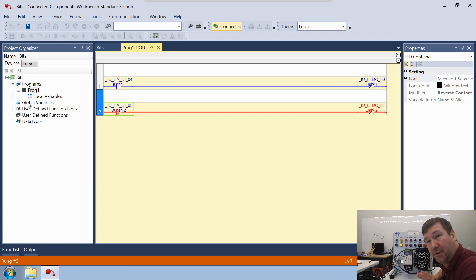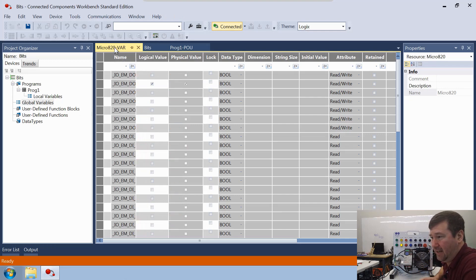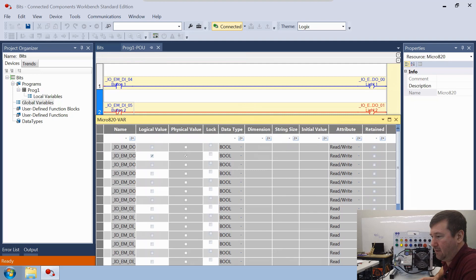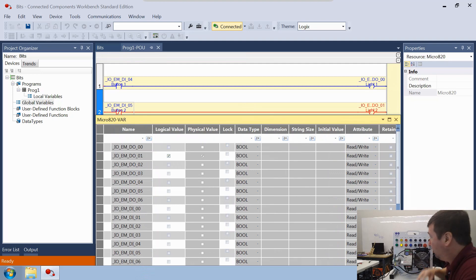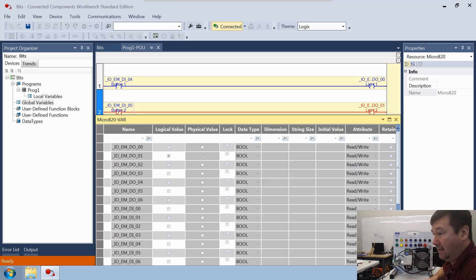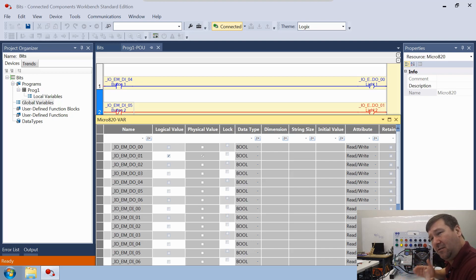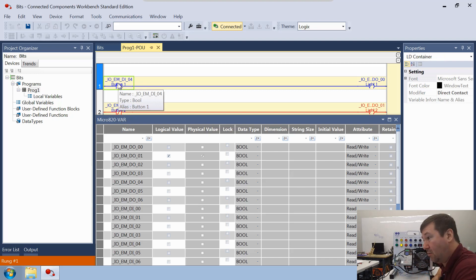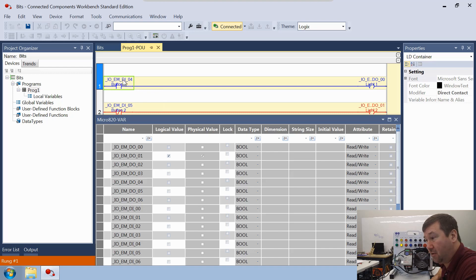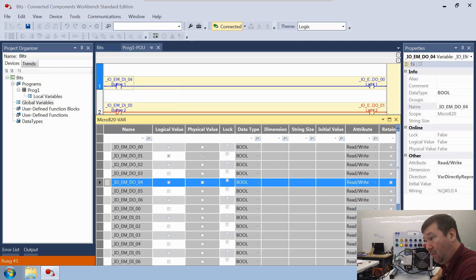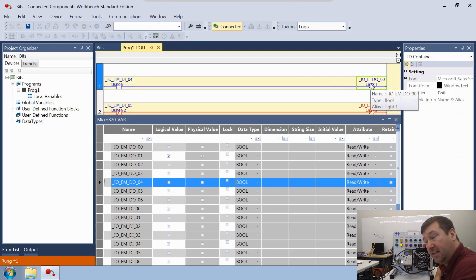Let's open up our global variables and walk through this program. You see this checkbox by Output 1 — that's also why Light 2 is on. Think of a checked box as a 1 and an unchecked box as a 0. So now let's look at these instructions. This Direct Contact says: go look for a 1. Where? At Input 4. Do I have a 1? No — so I'm going to be false, shown by the blue. Going over to our coil with false conditions — what does a false coil do? It writes a 0. To the address right above it, which is Output 0. So that's unchecking that box.